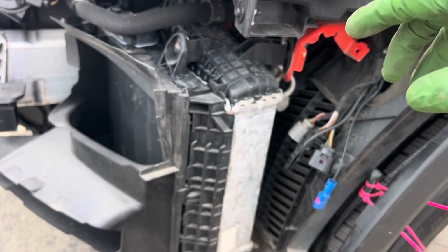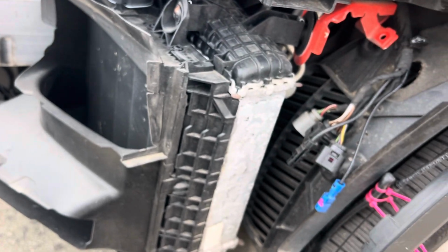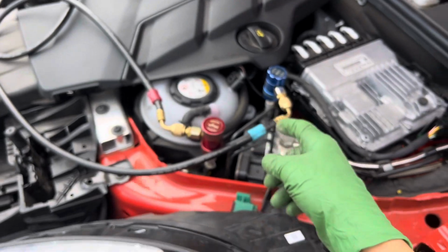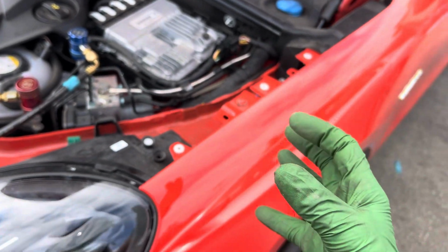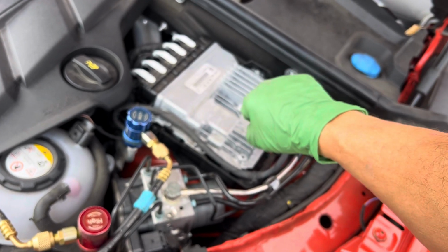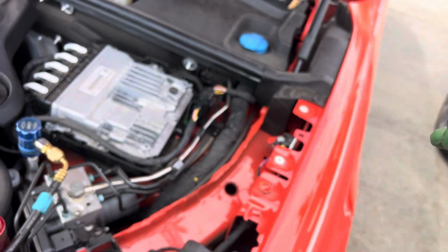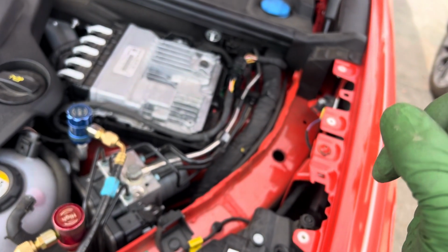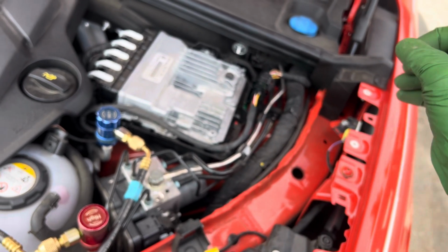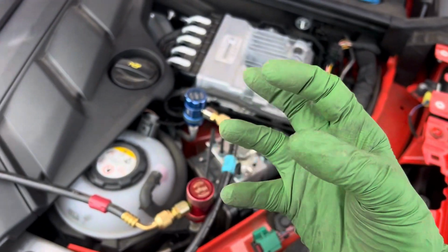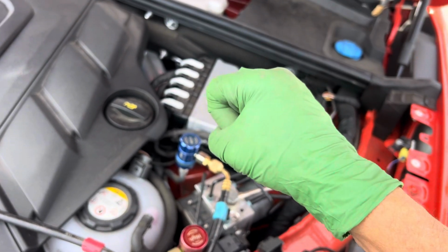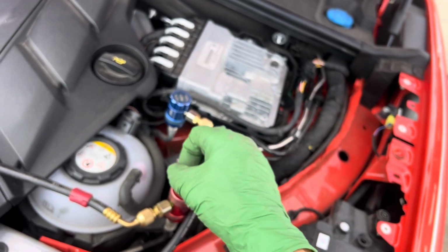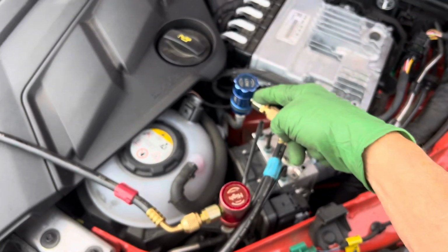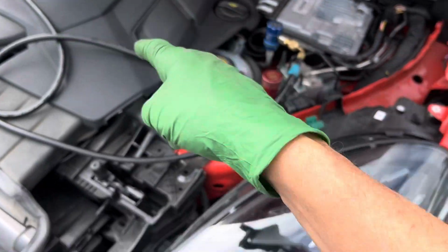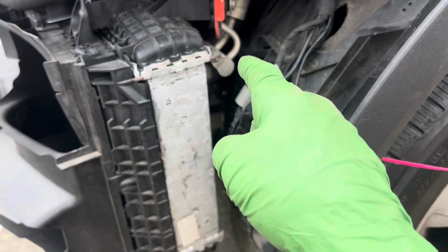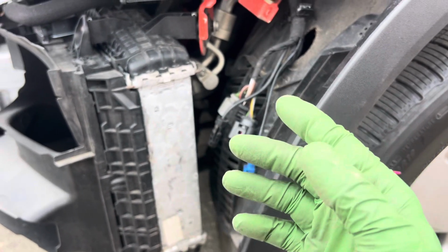So when you drop the pressure, that oil is turning into a foam, and the refrigerant travels up towards here. And just like when you shake up whipped cream, it has nitrous oxide in it, and when it goes into a lower pressure, the atmosphere, it's like CO2 and Coca-Cola. When it hits the atmosphere, because it's in a thick buttery form, it foams up like styrofoam, or like Great Stuff, that expanding foam at Home Depot. It foams up, it travels up the tube, and all the refrigerant oil gets sucked out into your recovery machine. So that is what's causing that, and I had to know why, because it's just how I am.